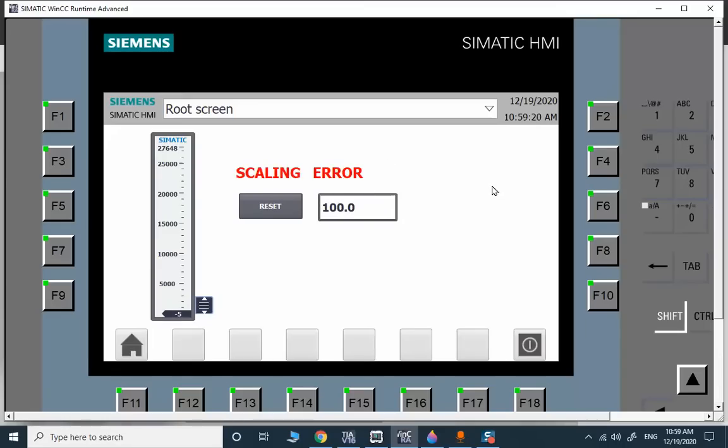This is the purpose. There is a safety purpose behind this option. When we have under range or over range, we will select the safest value. In this case, we are scaling a temperature value from an analog card, analog module. The maximum scale value will be considered as the output.